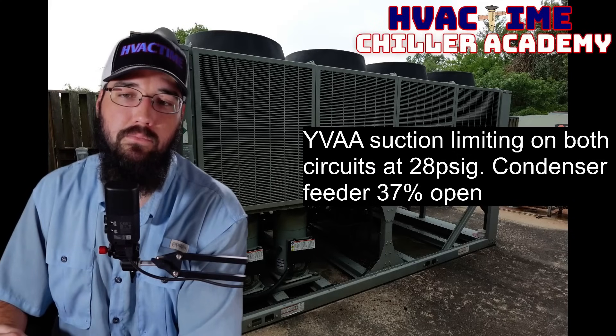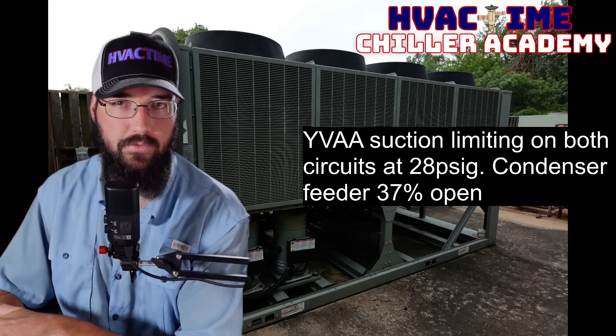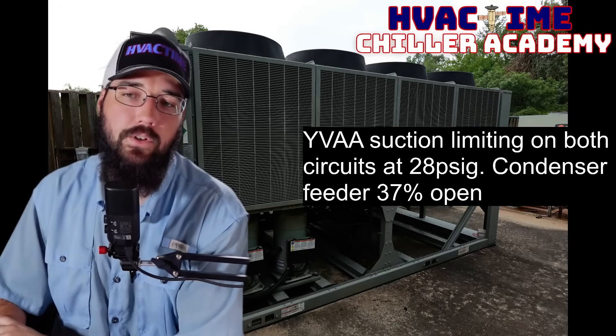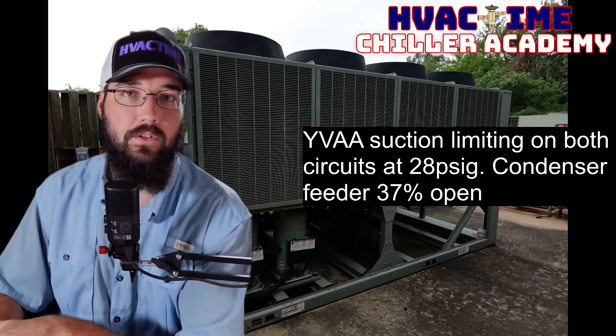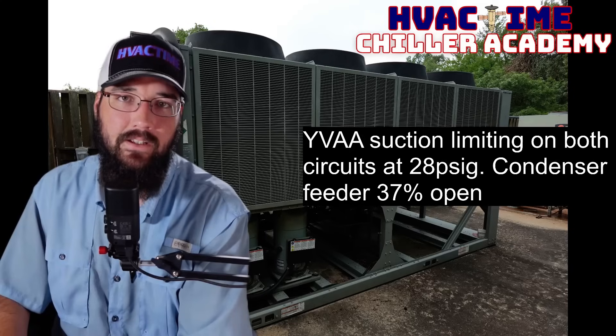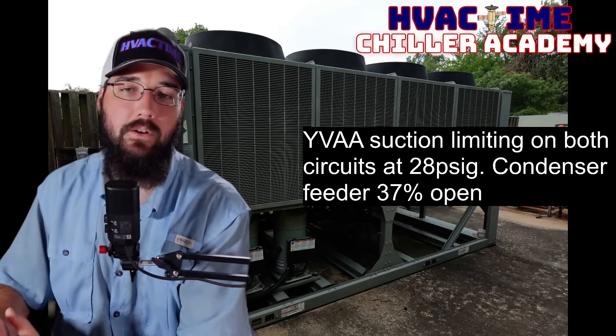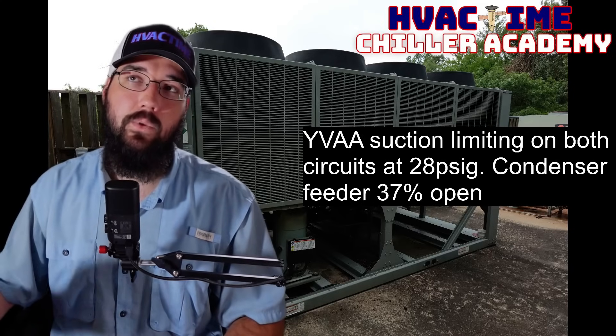Because it is both circuits, and usually both circuits don't — if you had a low charge, for example — both circuits rarely leak at the exact same rate. These are independent circuits on these machines. So being that they're both operating identically, I would say that it's probably not a refrigerant issue.